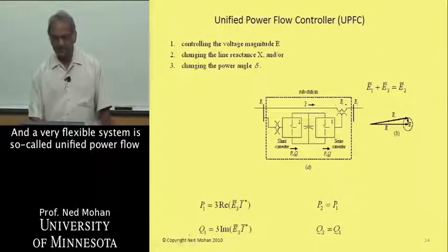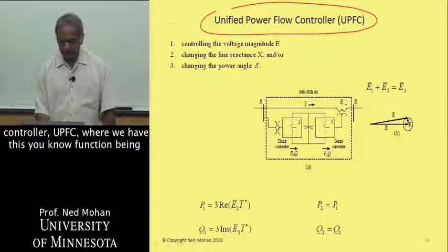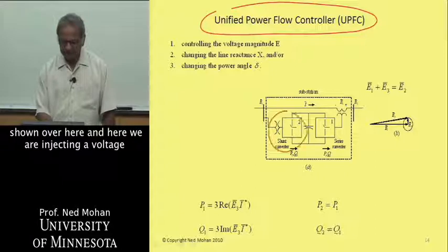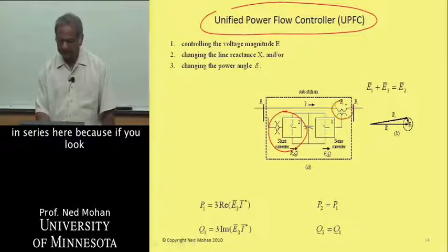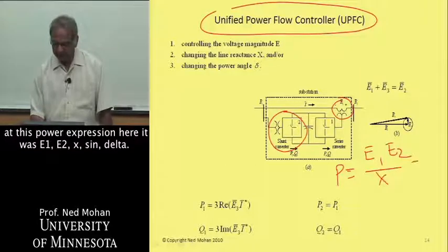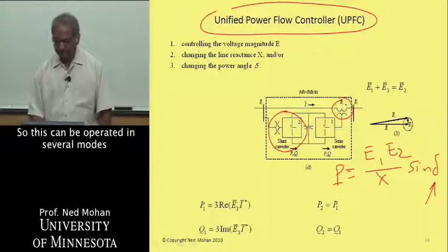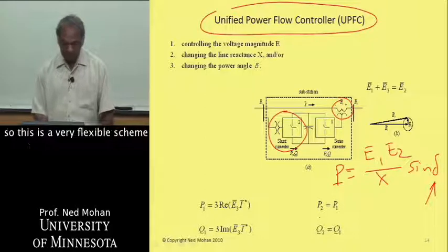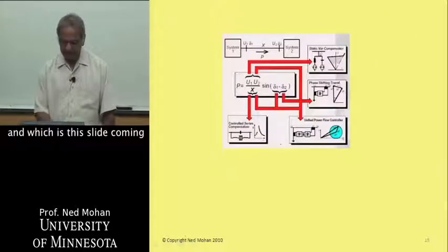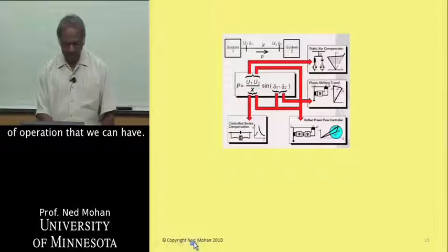A very flexible system is the unified power flow controller, or UPFC, where we have a STATCOM function shown here, and we inject a voltage in series. Looking at the power expression, it's E1 times E2 over X times sine delta. If you can control delta, you can also control the power flow. This can be operated in several modes, making it a very flexible scheme. This slide from Siemens shows the different modes of operation.